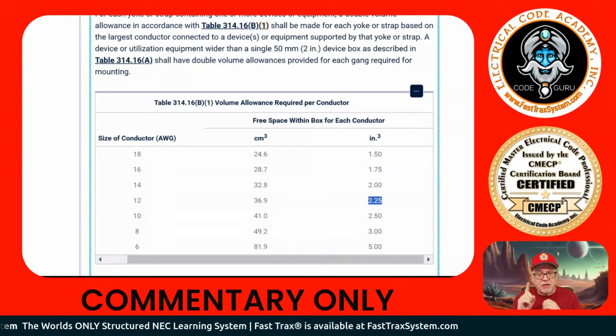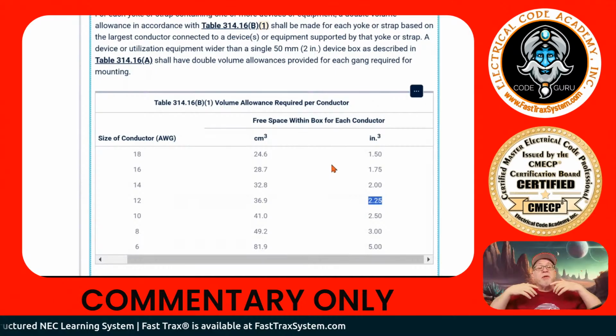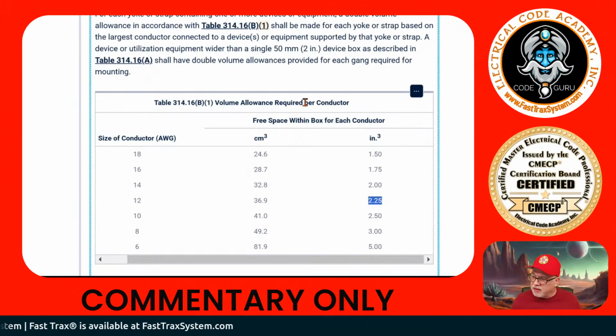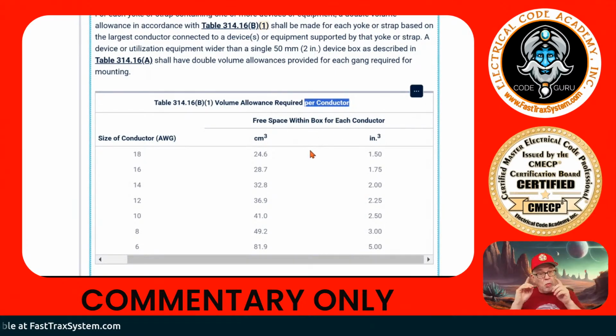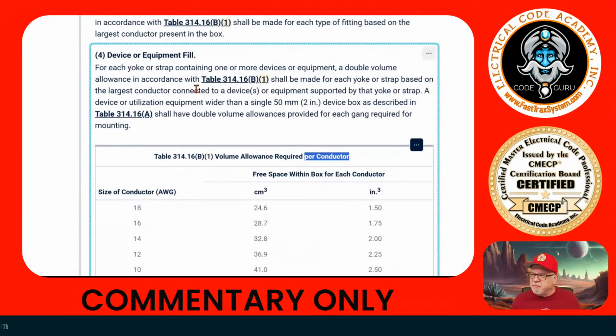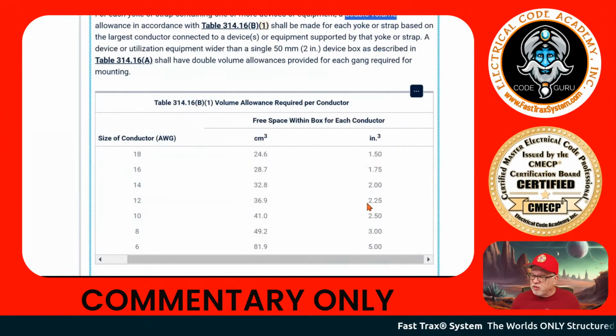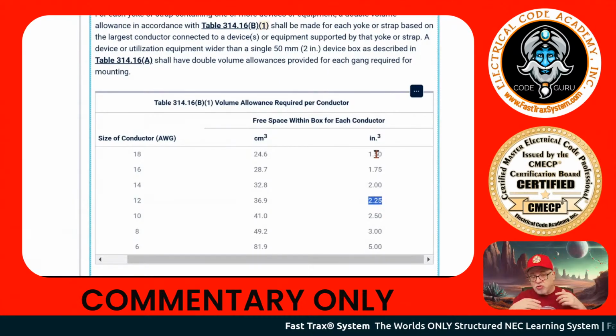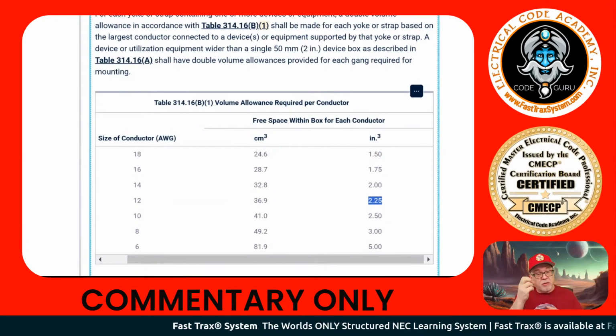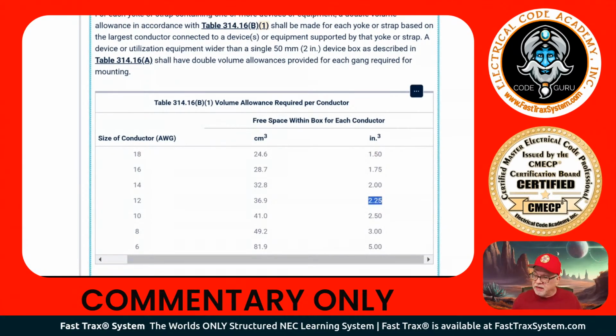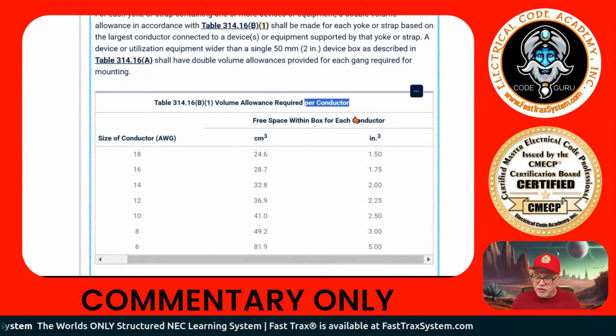But that's for one conductor. Remember, that represents one conductor. Notice up here it says per conductor, one conductor. Up here, it made it very clear that it's a double volume. So it equates to 2.25 if it was 12 gauge times 2 because it was 2 conductors, right? Because this 2.25 is per conductor.